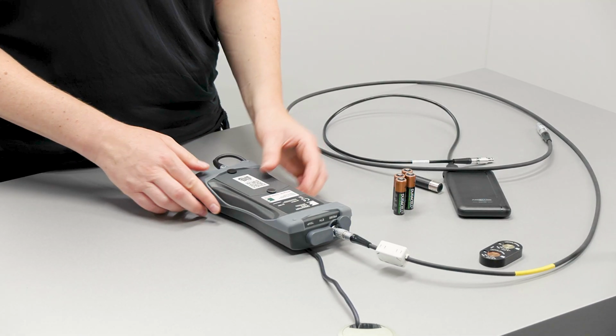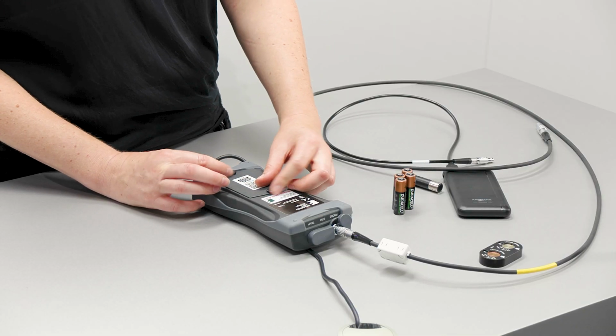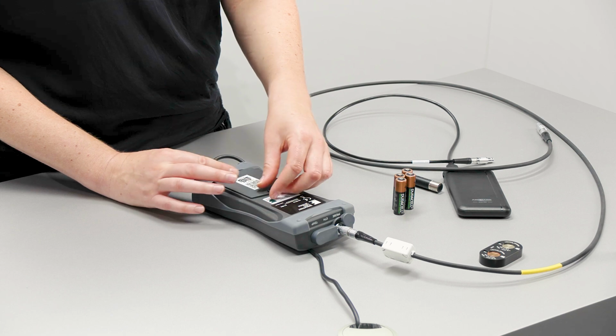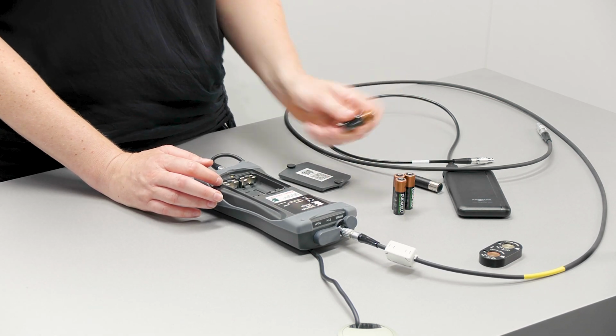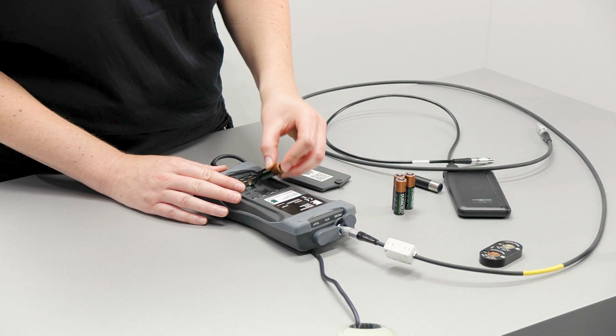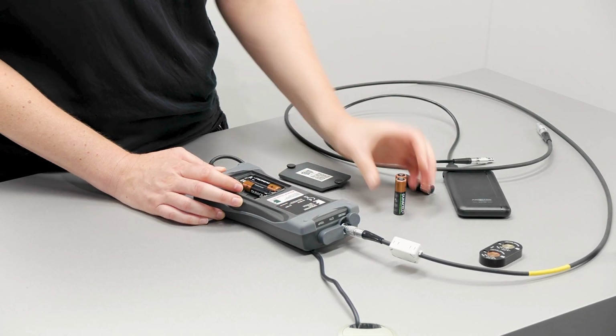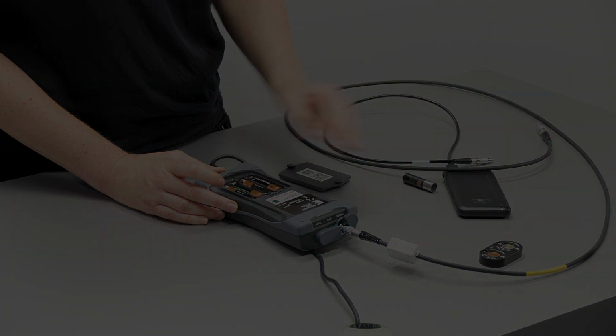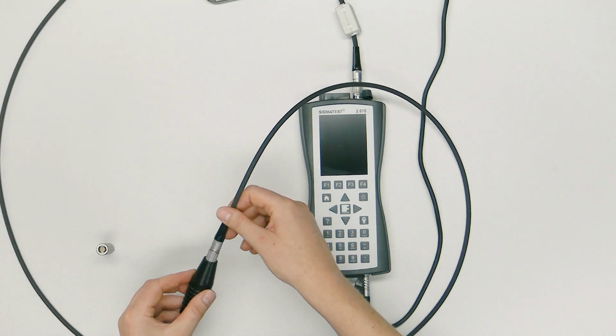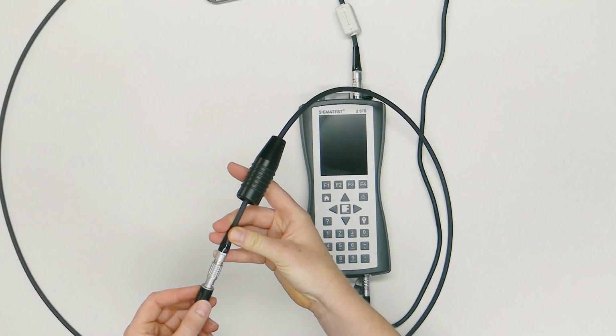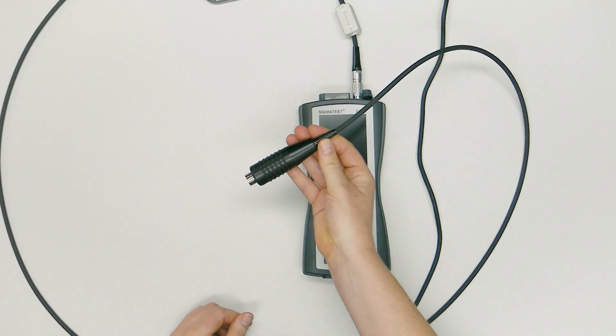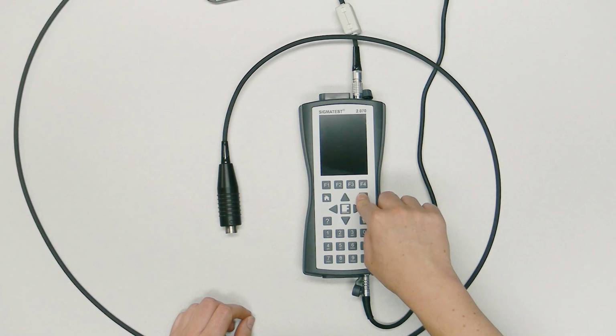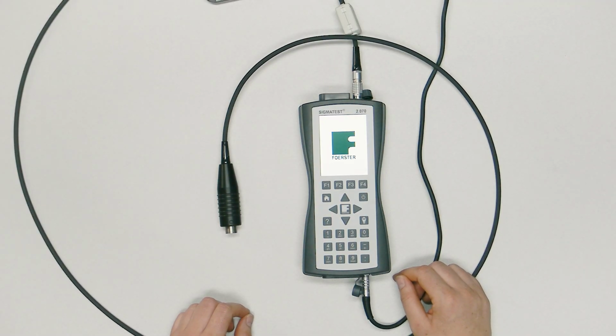Insert additional batteries or rechargeable batteries into the battery compartment of the device if necessary. Ensure that the polarity of the batteries is correct. Put the holder onto the cable before you plug in the probe. Switching on and off is done via the on-off button. I press and hold the on-off button for approximately 1 second, then I release the button. To obtain precise measurements, the device must warm up for approximately 30 minutes before the first measurement.